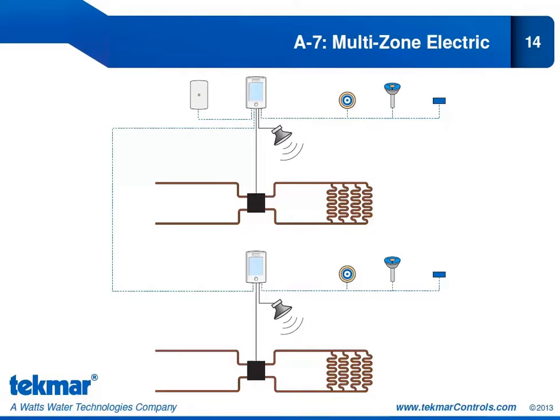Welcome to our last application, which is application 7, a multi-zone electric application. Here we are showing two snowmelt zones. We can in fact have up to 12 zones with the snowmelt control 654. Each of the zones is controlled by its own 654, and we are connected to our three sensor options, the 090 or 094, the 095, and the slab sensor 072 or 073. Now each of those 654s is connected to an electrical contactor, which in turn is going to energize the electric cables for the melting operation.